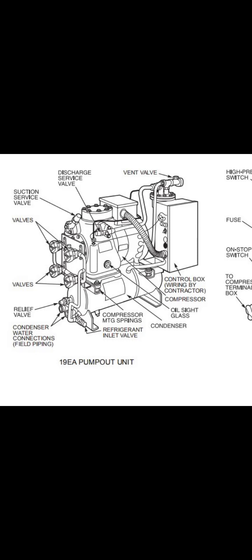You close the pump out system, close all valves. This is the procedure to pump down or pump out. In this case, the chilled water and condenser water must both be running. In other cases, you want to pump out the system and remove all refrigerant from the chiller.